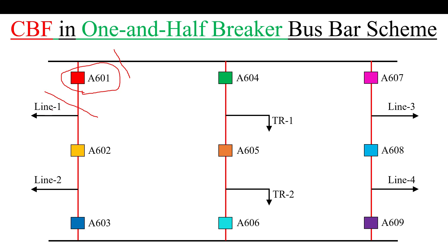If any one of the five failure conditions occurs to A601, its CBF relay will operate and send a tripping command to the other associated breakers. On the right side we have A604 and A607, so the CBF relay of A601 will send its tripping command to A604, A607, and on the other end to A602 and also to the line going to the remote end station.